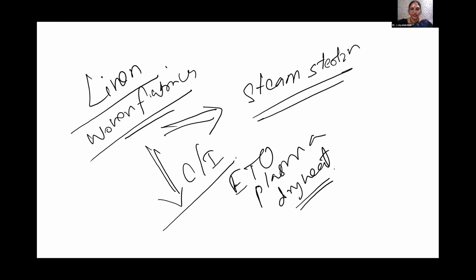One more thing I want to add here, ma'am: the inspection of the linen is very, very important before we use it. Prior to each use, the linen has to be inspected properly for the presence of holes, any stains, or any deposits. Sometimes the linens may have holes, so those things have to be checked very carefully; the person packing has to be very keen to inspect the linen properly. Double wrapping is another important thing which is recommended when we use linen.